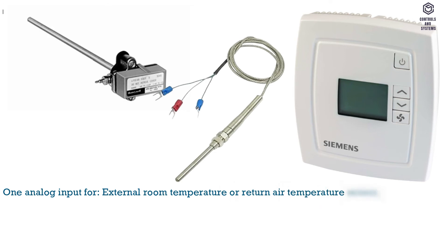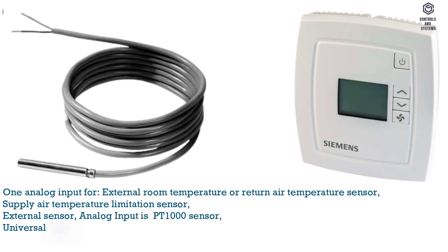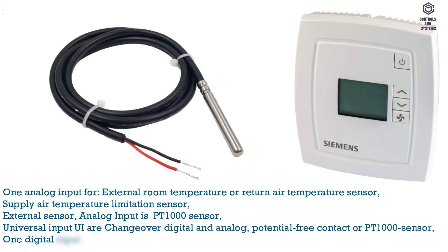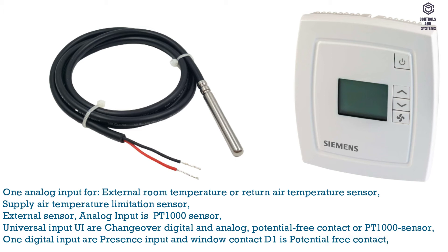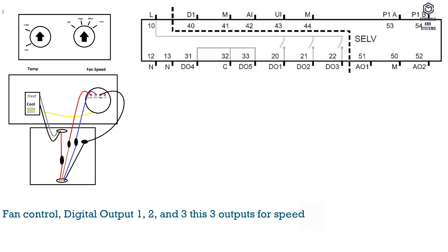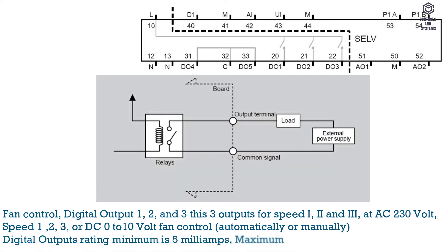Inputs: one analog input for external room temperature, return air temperature sensor, or supply air temperature limitation sensor. External sensor analog input is PT1000. Universal input (UI) is changeover — digital and analog potential-free contact or PT1000 sensor. One digital input: presence input and window contact (D1) is a potential-free contact. Outputs — fan control digital outputs 1, 2, and 3 are the outputs for speeds 1, 2, and 3 at AC 230 V, or DC 0–10 V fan control, automatically or manually.